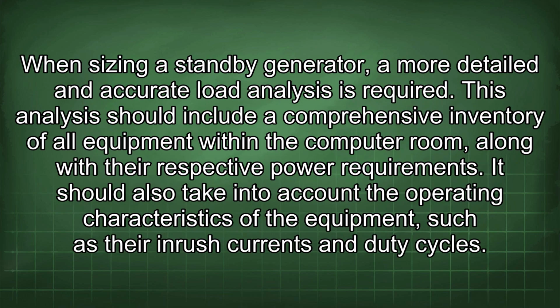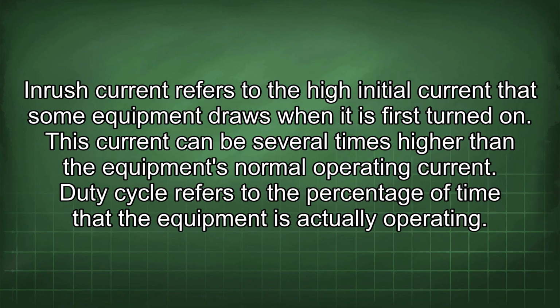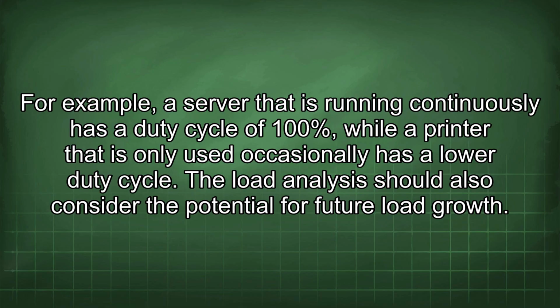When sizing a standby generator, a more detailed and accurate load analysis is required. This analysis should include a comprehensive inventory of all equipment within the computer room, along with their respective power requirements. It should also take into account the operating characteristics of the equipment, such as their inrush currents and duty cycles. Inrush current refers to the high initial current that some equipment draws when it is first turned on. This current can be several times higher than the equipment's normal operating current. Duty cycle refers to the percentage of time that the equipment is actually operating. For example, a server that is running continuously has a duty cycle of 100%, while a printer that is only used occasionally has a lower duty cycle.